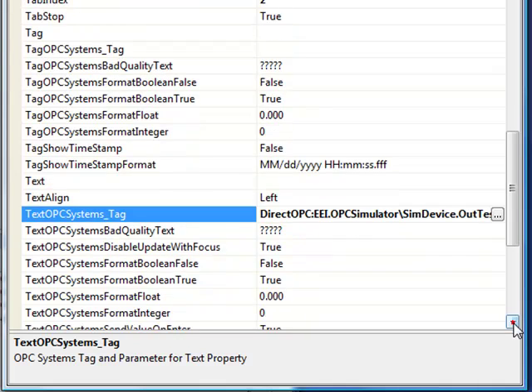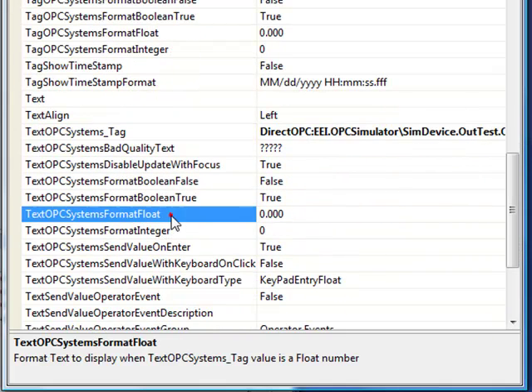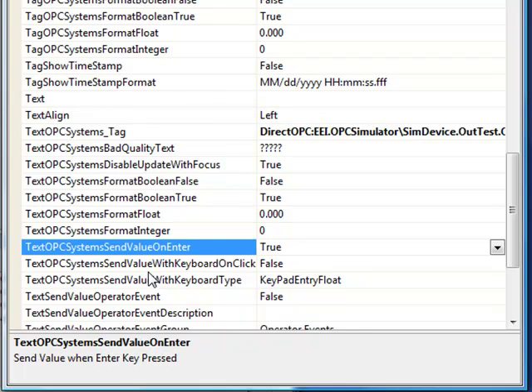Now, under the text property, we want to take a look at what is the format that's going to be displayed for that float signal. Right now we have 0.000 with three digits to the right of the decimal point for the resolution. We want to leave the property text OPC systems send value on enter at true. This allows the operator to send a value when they have the cursor on the text box and hit the enter key, whatever text is in that text box will be sent to the tag defined under text OPC systems underscore tag.